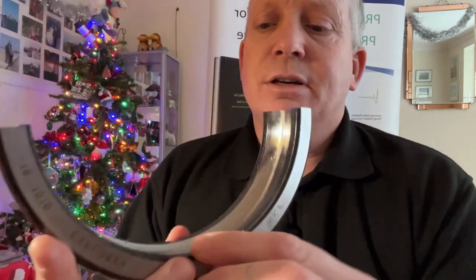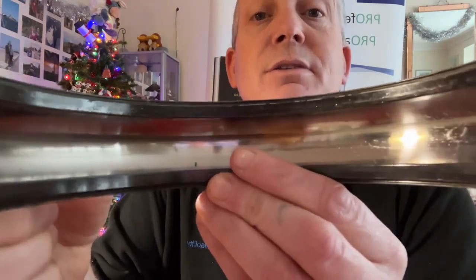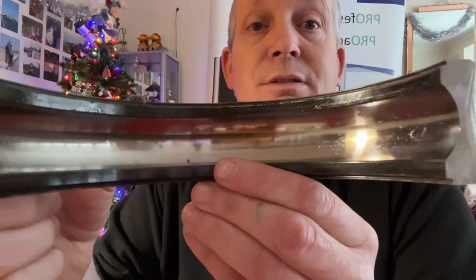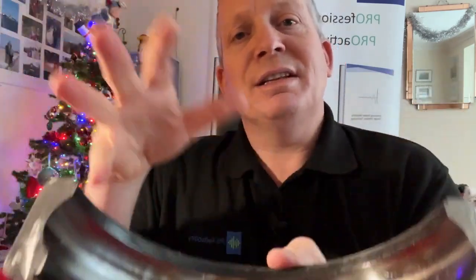Now, because it's an outer race bearing, it's stationary, so we'll have a load zone and a non-load zone. In the non-load zone, all the way around the bearing, you can see a tiny little grey line. That grey line is, again, an issue with the earthing and the setup of the drive. And the actual defect, which we predicted, you can feel with your fingernail. As it comes into the load zone, it gets thicker and thicker. It's really hard to capture, but we'll see it in a minute in the close-up images with the microscope. So that there is the defect, and you can pick at it, so it's just before it's going to spall out.